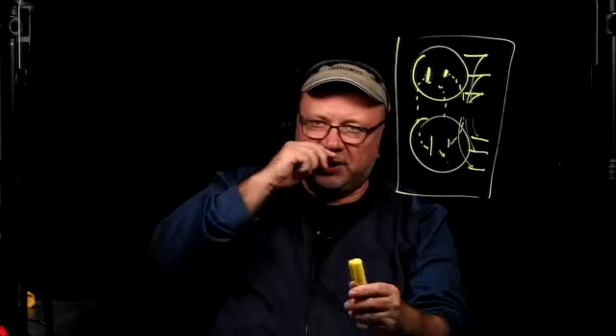Those devices combined together may request more current from the circuit breaker than the circuit breaker is designed to give. And if it requests more, the circuit breaker says no, it's just going to flip and disconnect. So that's why around the kitchen cupboards, we are mostly using split receptacles. Basically, if it's 15 amps and 15 amps, then you have 30 amps total in that whole thing, instead of just 15 if it was not a split receptacle. Right?